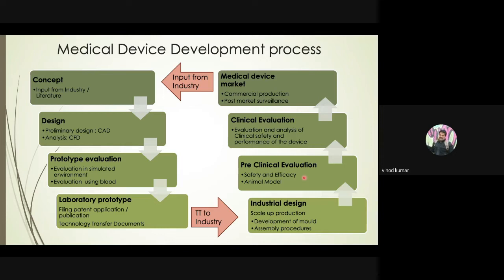Suppose it is a medical device like a heart valve, you may have to implant the device in animals like sheep or pig. Let it run for a few years to understand the behavior of the device in the biological system and the behavior of the biological system with the presence of the mechanical device. And there is another phase coming along with this safety and efficacy evaluation, like the functional evaluation. That's called the biomaterial evaluation. Any medical device is made with biomaterials, or materials which are compatible with the biological system. So in certain places we may need totally inert materials which do not react with the biological system at all. Certain devices require that.